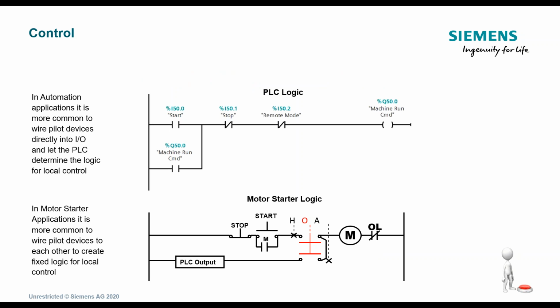So with control, here's just some simple ladder logic and also a simple control scheme of an HOA. You have right here start and stop, remote mode, and you have the ability to have an overload with the motor. So if something does go wrong in the process and the motor overheats, it'll trip. But here's just some simple common ladder logic for motors, where you have the start-stop circuit, and hand meaning that it's local, remote or off, or auto meaning that the PLC is in charge of turning the motor on and off, and so forth and so on.